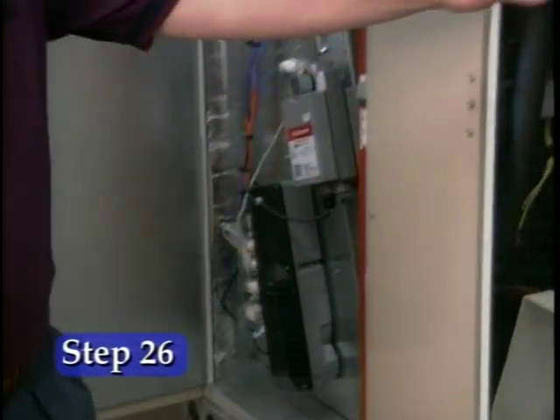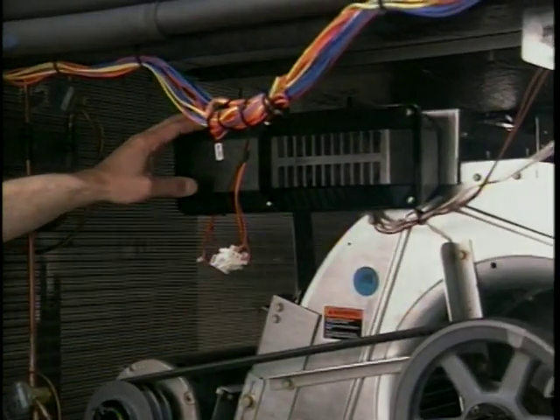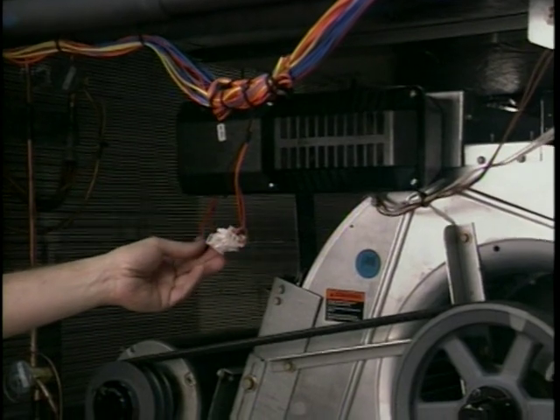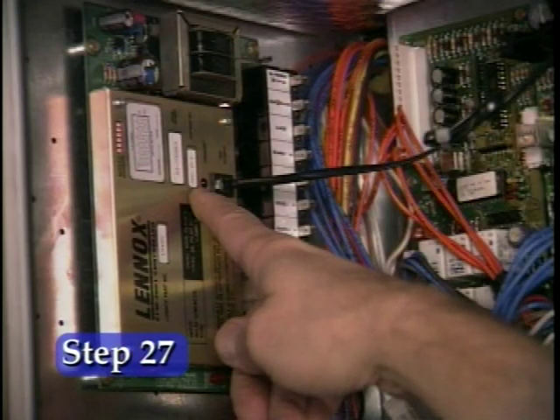Visually check if smoke detectors are present and wired. Do not test the smoke detectors. The following tests should not be done on units with DDC control. A feedback circuit will damage the DDC controller. Put a jumper on TB1 from terminal 3 to terminal 6.